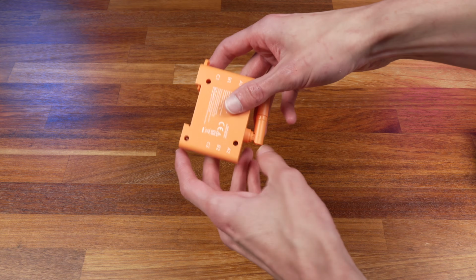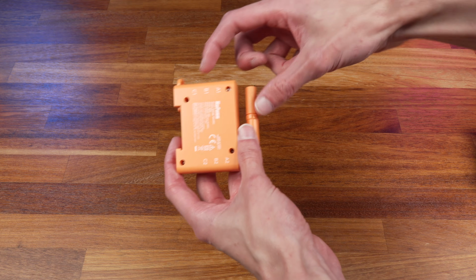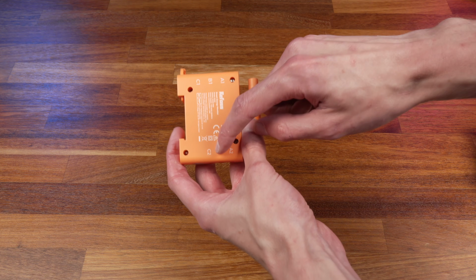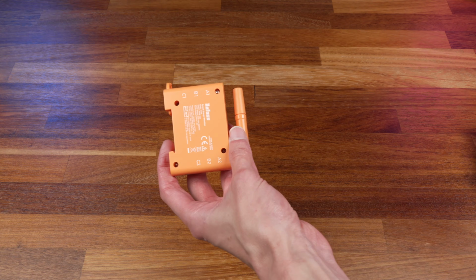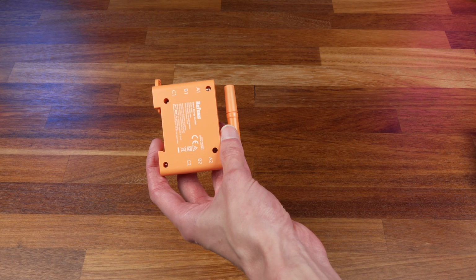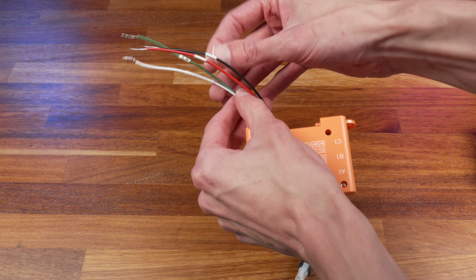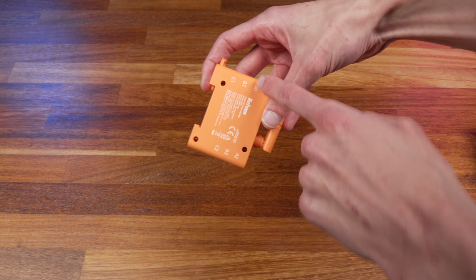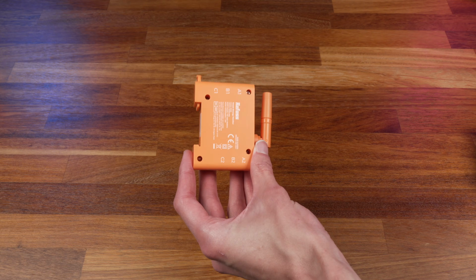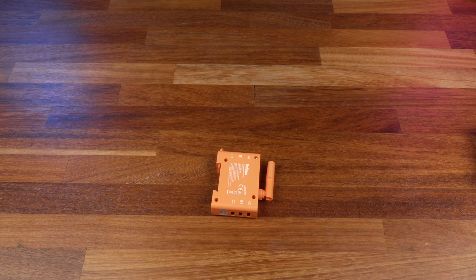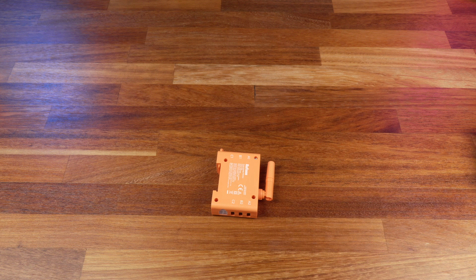Now you'll notice here that these CT connections have designations on them, so A1, A2, B1, B2 and so on. Those letters refer to the phase connections that they're referenced to. And as you can see on the power cable we looked at earlier, we have LA, LB and LC. So the letters after L refer to the letter on the CT connection. So what this means is that the CT you're connecting to the A inputs would need to be monitoring circuits on the same phase as the one that you've connected LA to on the wiring harness.